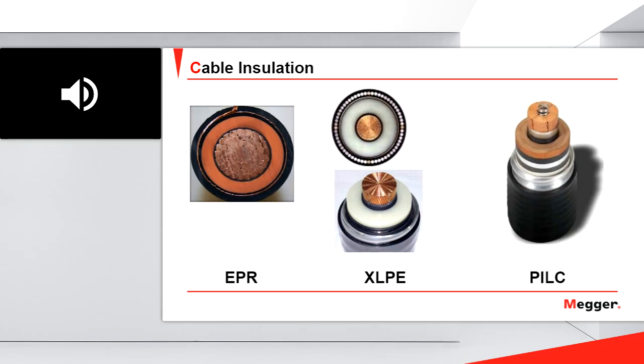So when I need to do a flashover, to create an arc at that fault, the voltage I will need is between 3 kV and 5 kV for a 15 kV cable, for instance. I will not need more than 5 or 6 kV to flash over the pinhole fault in my cable. But if I have the same pinhole in a paper insulated cable, the hole will be filled with oil, the dielectric oil. In this case, I will need more voltage and more energy to flash over the fault. So always when I have paper insulated cables, my thumper, my fault locator equipment, will need more energy and more voltage to flash over faults. This is something we need to keep in mind when we choose a thumper or a fault locator for our facilities or our cables.